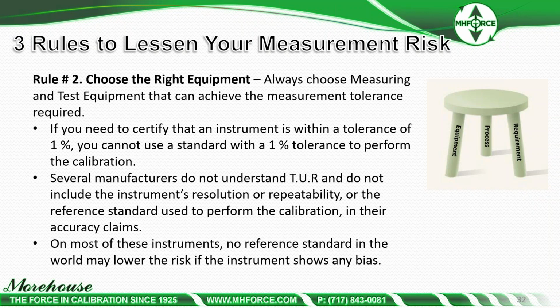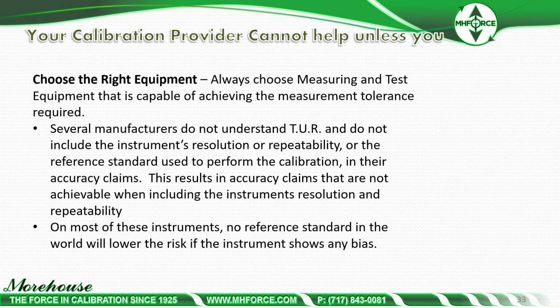Several manufacturers do not understand TUR and do not include the instrument's resolution or repeatability or the reference standard used to perform the calibration in their accuracy claims. Yep. Or they do understand TUR and they force it on the end user. They say, hey, we're not going to do it here, we're going to force it on the end user. On some of these instruments, no reference standard in the world may lower the risk if the instrument shows bias.